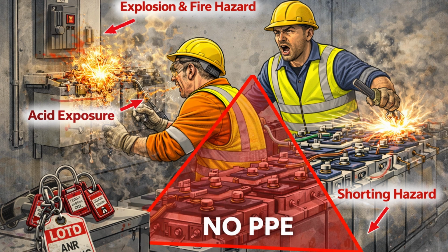In this scene, we see work being performed in a battery maintenance or charging area. However, multiple serious hazards are present. First, a short circuit has occurred on the battery system, generating sparks that may lead to fire or explosion hazards. Battery systems can also produce acid splashes or acid vapors, which can severely damage the skin and eyes of workers. Another critical issue is that the workers are not wearing appropriate personal protective equipment. There is no face shield, chemical-resistant gloves, or eye protection. Additionally, the equipment appears to be energized and lockout/tagout has not been applied. When working in battery maintenance or charging areas, energy isolation must be applied, proper PPE must be worn, and the work area must be properly controlled. Remember, when electrical and chemical hazards combine, a small mistake can lead to a major accident.